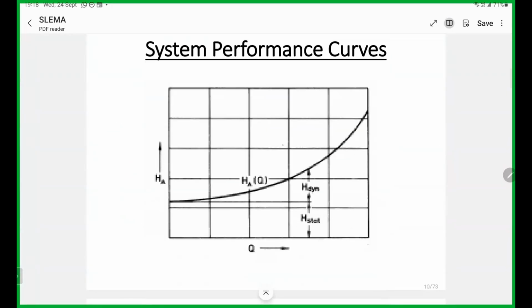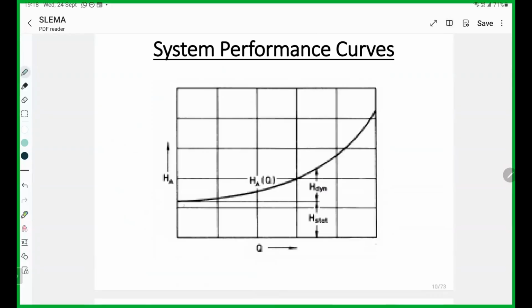This is directly related to the specific energy consumption. Right? Then if you think about this system curve, this is static head HS, then this is HF, right? Most of the cases we cannot reduce static head, but sometimes, in the waterboard context, we can reduce HS. But the important one is HF. How to reduce this HF? HF basically has two components, H major and H minor.